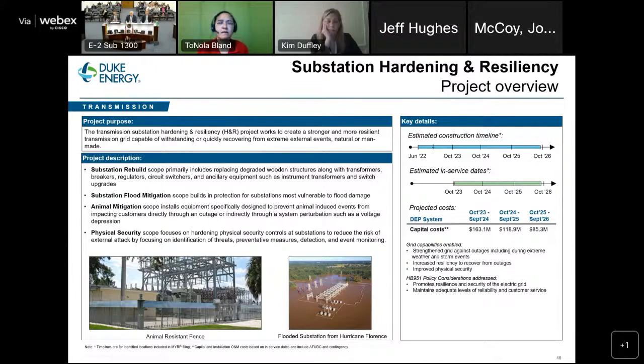Animal mitigation involves installing animal mitigation fences around our substations. Animals are a very significant contributor to transmission outages. When an animal contacts equipment inside a transmission station, the equipment is typically designed to lock out, so the breaker opens. This prevents more significant damage and collateral damage. When animals contact lines or circuits, that's not always the case. As mentioned earlier regarding momentary impacts, when animals impact substations it's often a sustained outage that affects customers. By installing specialty fences, we're preventing snakes, squirrels, and raccoons from getting into our stations, greatly reducing the chance of an animal causing an outage.